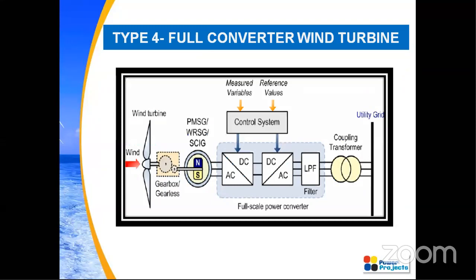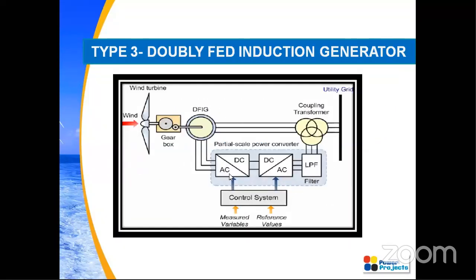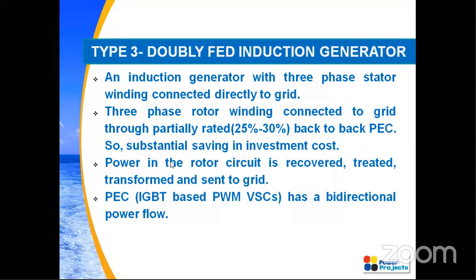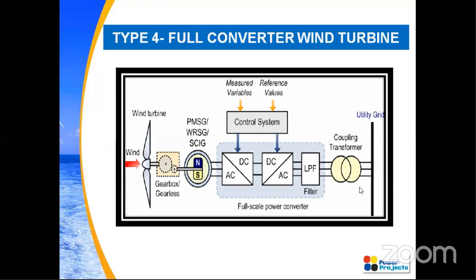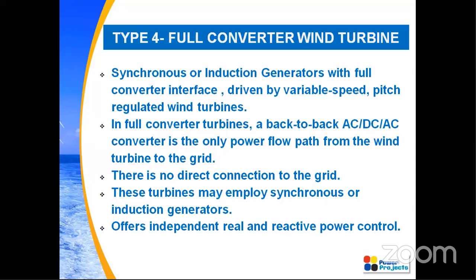Moving on to the next type, the full converter wind turbine. We will be using the same back-to-back converters, but one different thing between type 3 and type 4 is that it may be either a synchronous generator or an induction generator, and it is not connected directly with the grid. In the previous type 3, you could see it is directly connected with the grid and also through the back-to-back converter. But in type 4, the only path of connection between the generator and the grid is the full converter. This is an important note about the type 4 converter. And it offers independent real and reactive power control. That is a very important thing. And as I told, it may be either a synchronous or an induction generator.